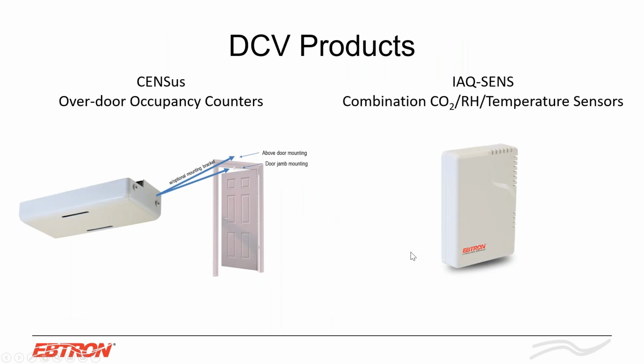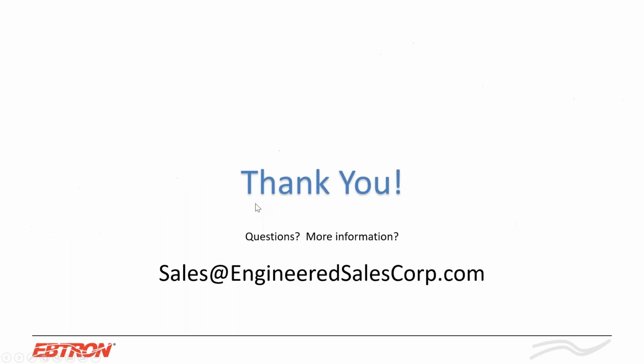And then to close, for CO2 DCV, again, we do have a relative humidity. We have a CO2 sensor, but really want to recommend setting those upper and lower airflow limits to save energy and to make sure you're not underventilating the space if you are doing CO2 DCV. But we also have the census occupancy counter. This is what it looks like. Goes over the door, and basically what it is, we have 2 thermopiles there, and it's measuring the thermal signature as you pass through it, and it sees a spike in thermal signature. And these are pretty cost comparable to what you'll see with the traditional self-calibrating CO2 sensor.